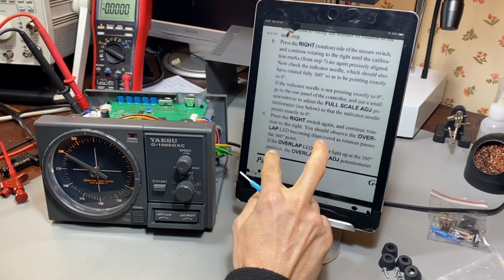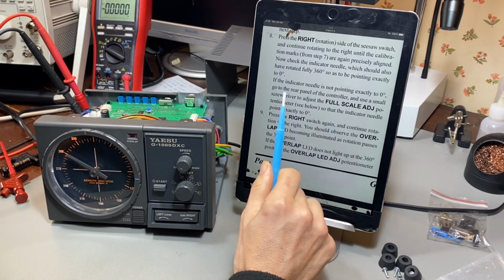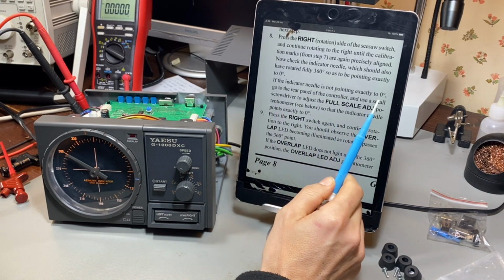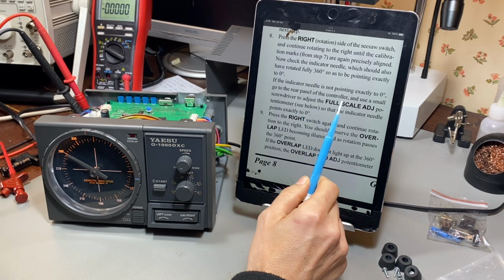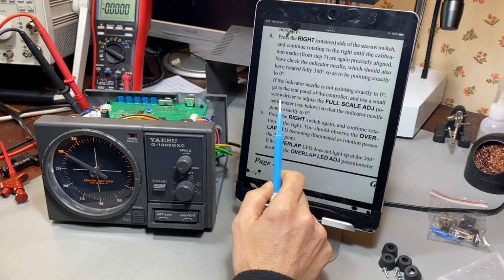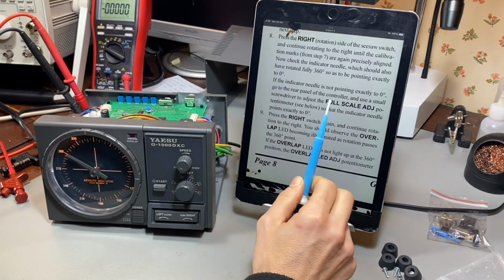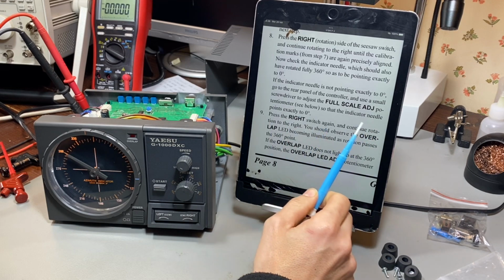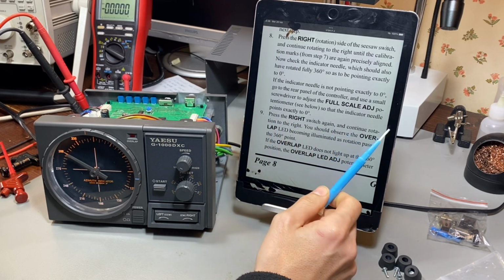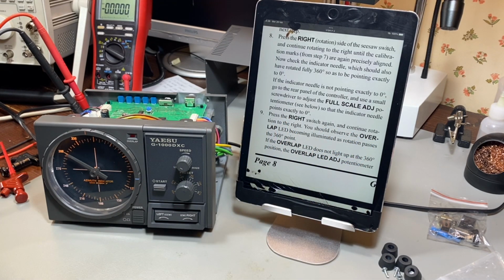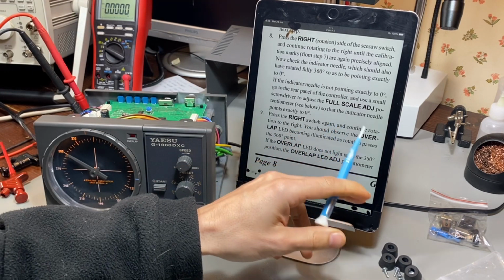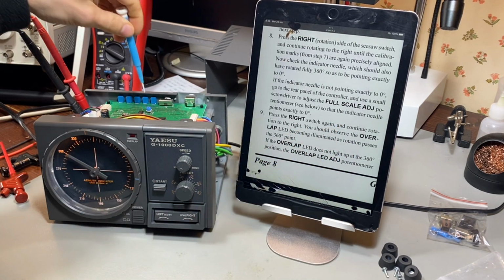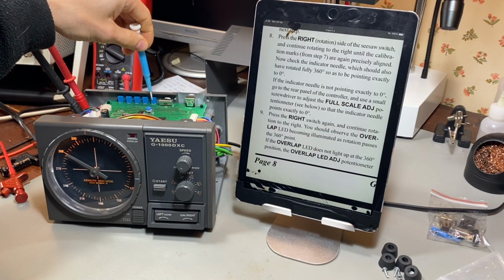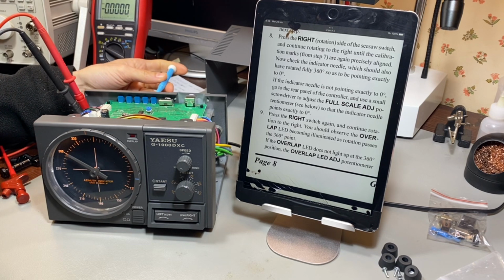As the manual says, if the indicator needle isn't pointing exactly at 0, go to the rear panel of the controller and use a small screwdriver like this one to adjust the full scale adjust potentiometer so the needle points exactly to 0. This full scale adjustment potentiometer is this one here, so let's go ahead and adjust it.